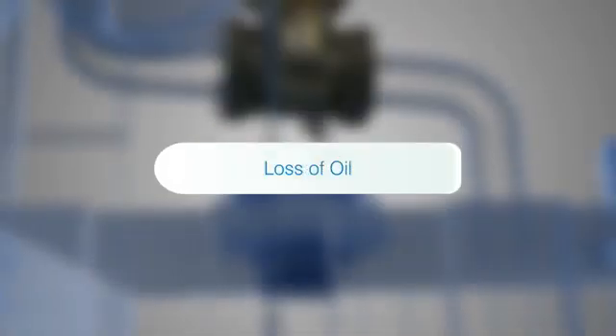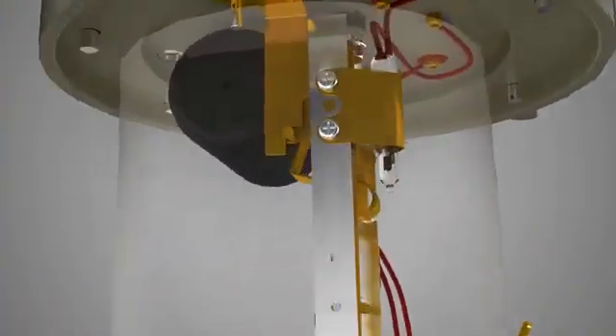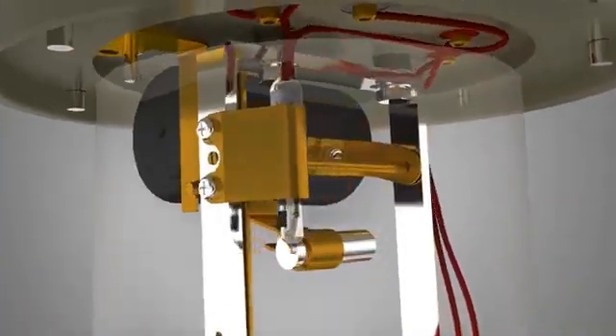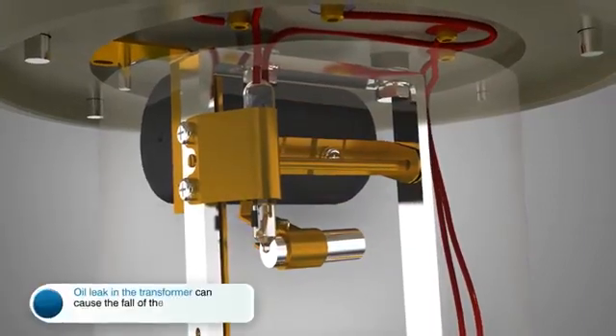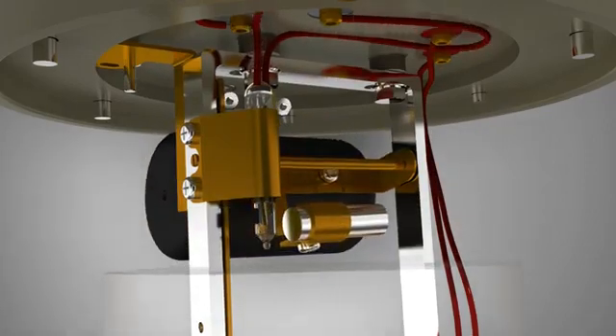Loss of oil: Oil leak in the transformer can cause the fall of the oil level inside the conservator and subsequently in the Buchholz relay. The falling oil level operates first the alarm.